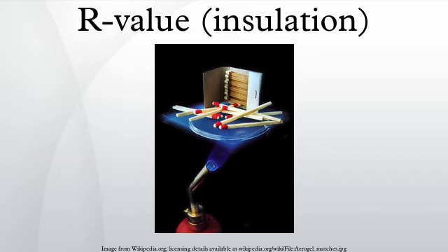When installed between wall studs, even perfect wall insulation only eliminates conduction through the insulation but leaves unaffected the conductive heat loss through such materials as glass windows and studs. Insulation installed between the studs may reduce, but usually does not eliminate, heat losses due to air leakage through the building envelope. Installing a continuous layer of rigid foam insulation on the exterior side of the wall sheathing will interrupt thermal bridging through the studs while also reducing the rate of air leakage.